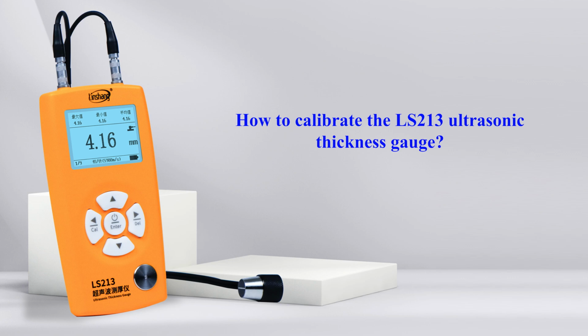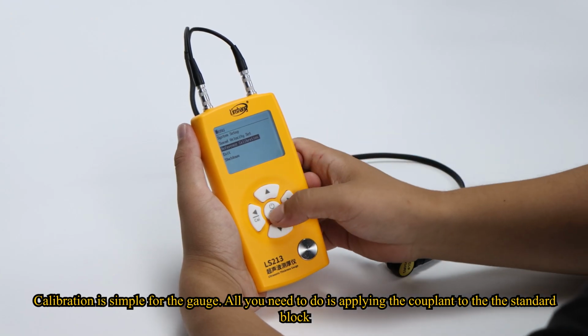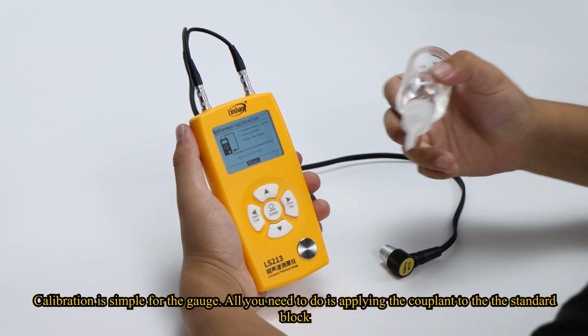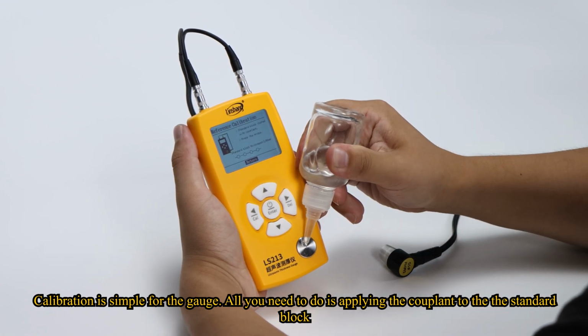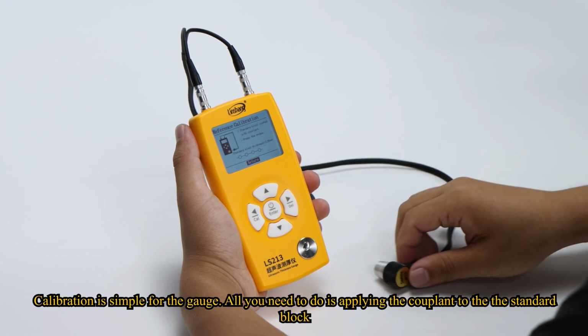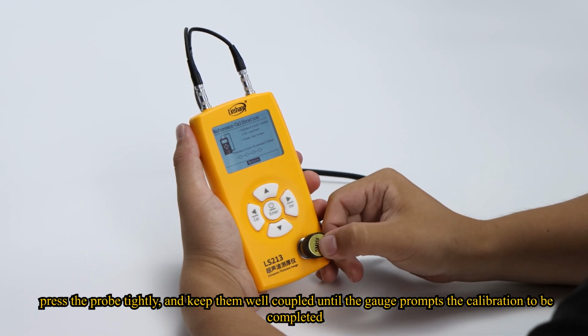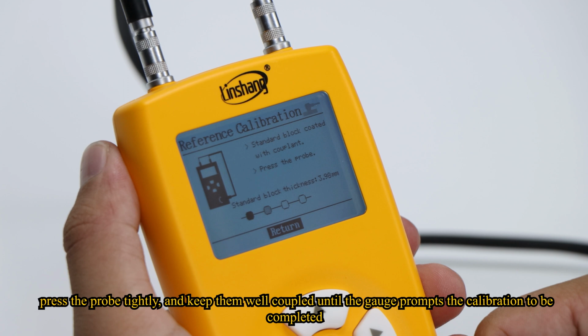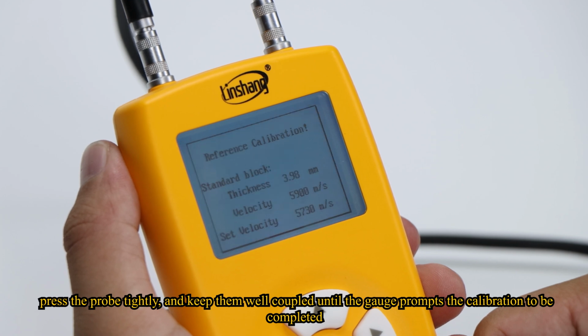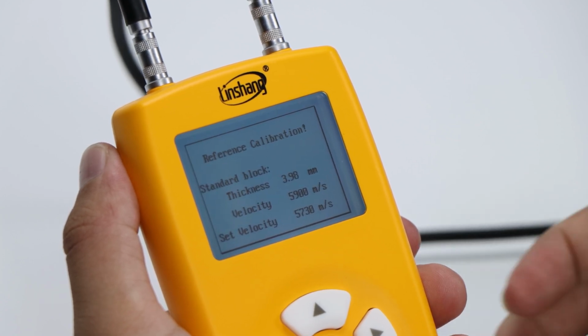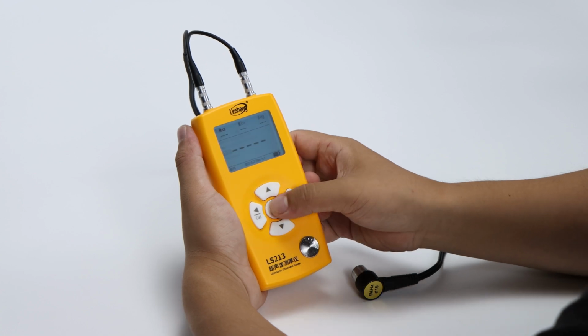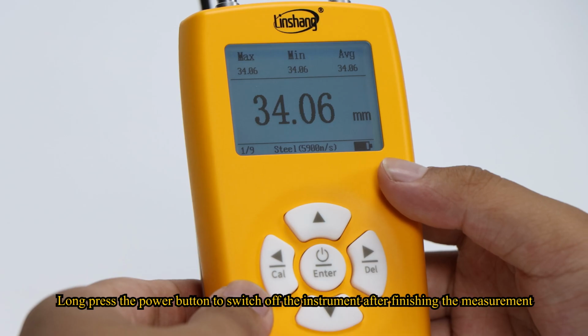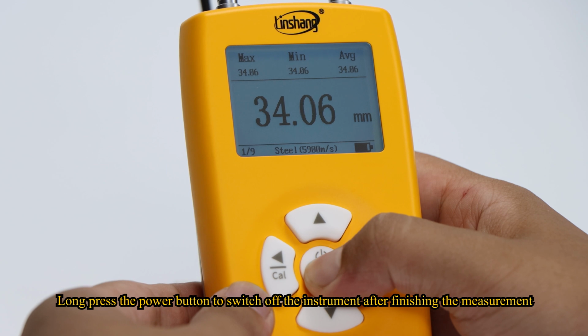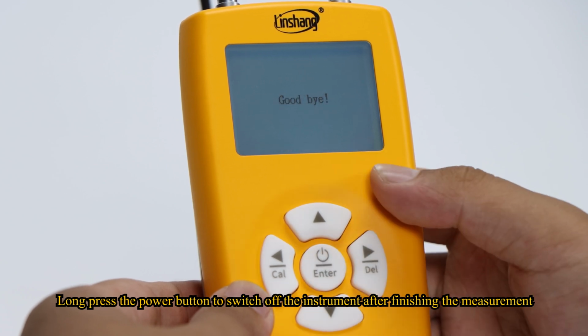How to calibrate the LS213 Ultrasonic Thickness Gauge? Calibration is simple for the gauge. All you need to do is apply the couplant to the standard block. Press the probe tightly, and keep them well coupled until the gauge prompts that the calibration is completed. Long press the power button to switch off the instrument after finishing the measurement.